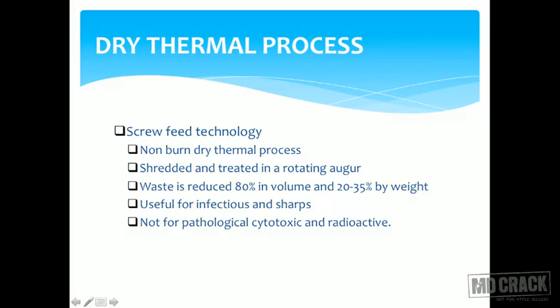This is a non-burn dry thermal process. You don't ignite like an incinerator, you just heat it, shredded and treated in a rotating auger so everything is finely chopped and destroyed. Waste is reduced by 80% in volume and about 20 to 35% by weight, achieving the objective. It's useful for infectious waste as well as sharps—imagine a sharp object getting shredded, mutilated, unusable, and made safe. It's a good method.